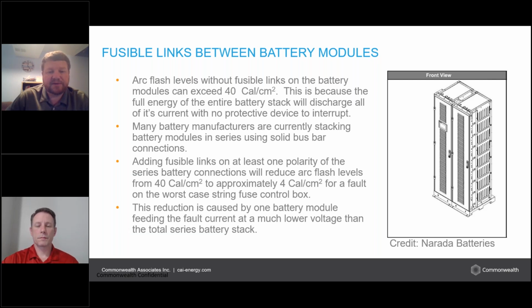So here's an example on the same example. If we were to use these fusible links between the battery modules, we could take an arc flash hazard level that's over 40 cals, which requires the full suit that has a rating of that same rating or higher, and reduce it down to a much more manageable level. By putting fusible links here, with some calculation, we found that we can knock that 40 cal arc flash hazard level, I think it was about 45 was the actual calculated value, down to just under 4 cals. And the nice thing about knocking it down to 4 cals is that's a very reasonable amount of PPE to be worn in the field. So that is very helpful.